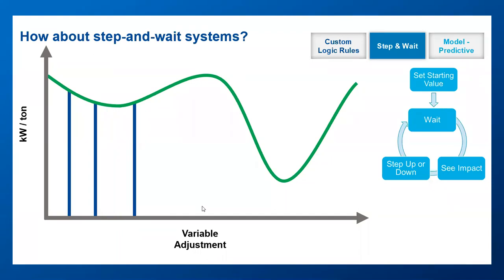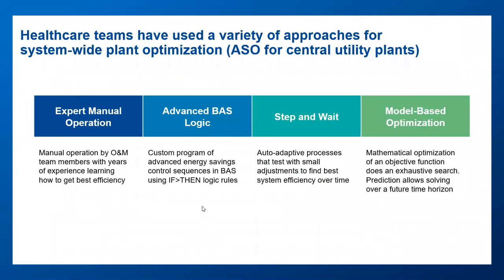The last approach we'll talk about is model-based optimization. This uses a more predictive approach, using a model of the building, or in this case the plant, and using math to do an exhaustive search of all the different potential combinations of set points. By set points, I mean both equipment selections and staging, binary set points like which equipment is on or off, and analog set points like temperatures, pressures, and flows, depending on how the plant is controlled. This model-based approach uses math to solve for the best set points that minimize an objective function, often energy cost to run the plant, but it could also be carbon or other things.